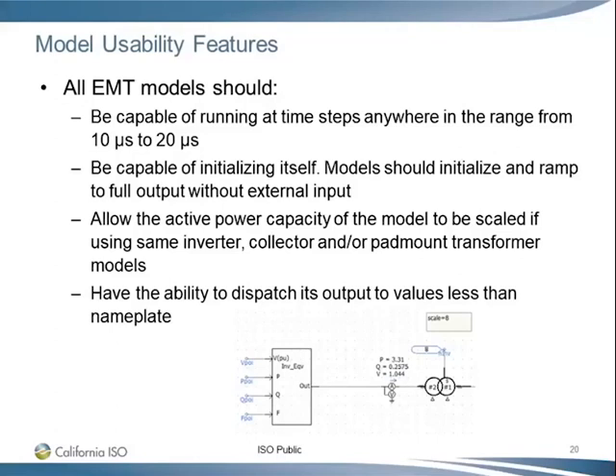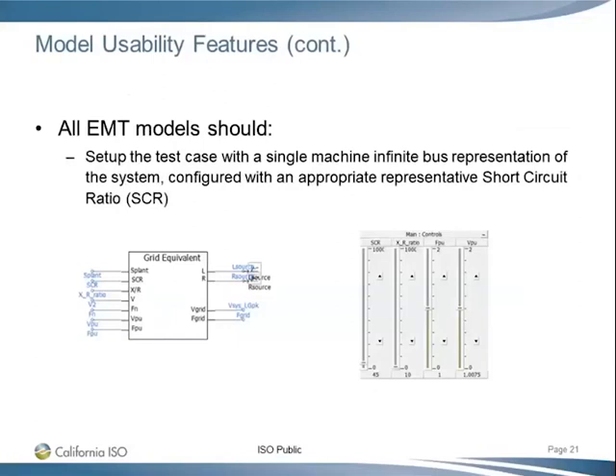Now, of course, it should initialize itself. We ask it to reinitialize itself within 5 seconds. Taking longer than that is considered bad model development. And then after the initialization, the model should be able to ramp up to the full output and settle there. Now, it should allow the active power capacity of the model to be scaled if using the same inverter, and also we scale up the number of inverters. Should be able to scale up the collector and transformer model. Then it should have the ability to dispatch output anywhere between 0 and the maximum output. The next slide.